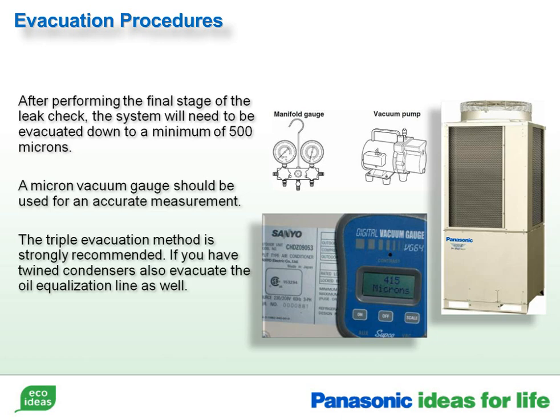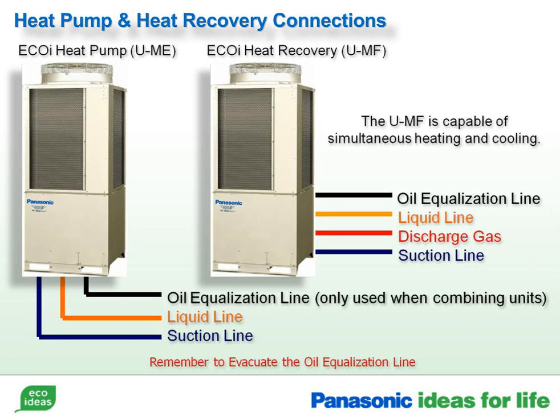The triple evacuation method is strongly recommended. If you have combined condensers, also evacuate the oil equalization line. Always apply power to the condensers for a minimum of 12 hours before starting up the system. The UME is a heat pump. It will only have liquid and suction lines.